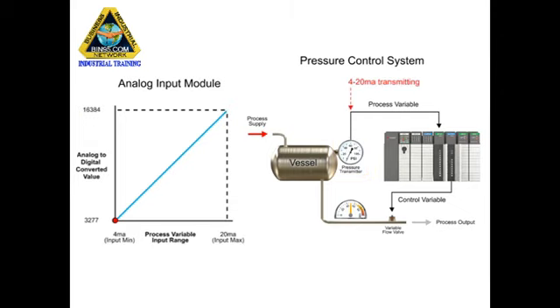The analog input module converts the 4 to 20 milliamp signal to a digital value ranging from 3277 to 16384. A 4 milliamp signal results in a value of 3277 and a 20 milliamp signal results in a value of 16384.